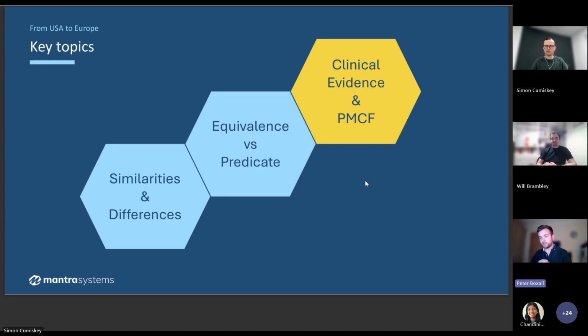And it's also useful going forward to look for systemic misuse of your device. So are clinicians and laypersons using the device as it was intended? And if not, what does that mean for your benefit risk profile going forward?